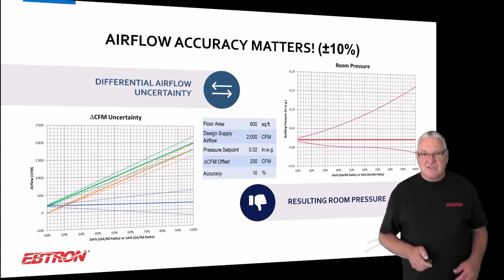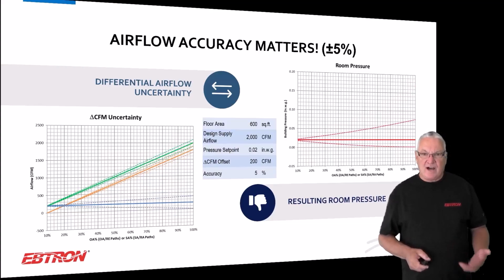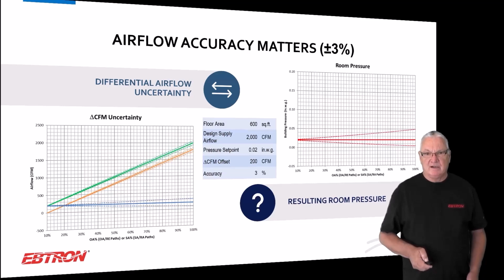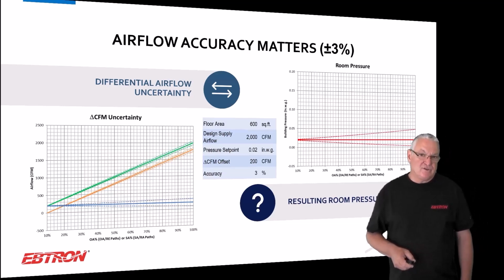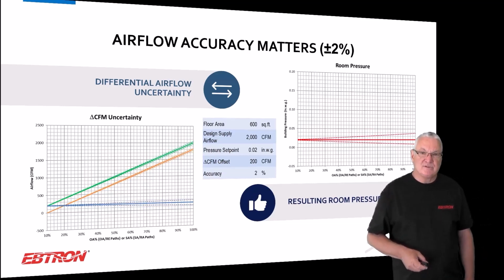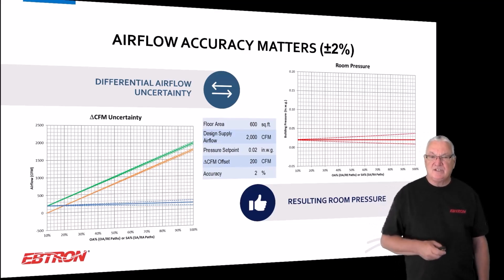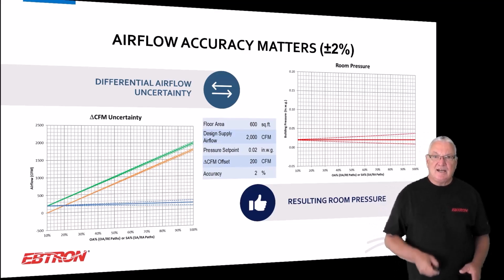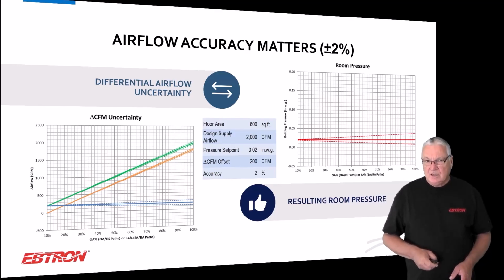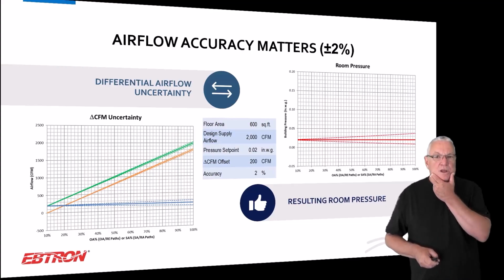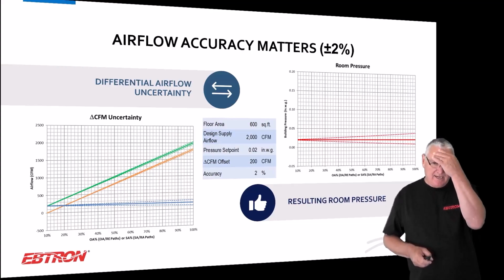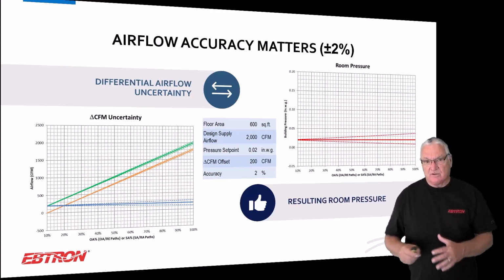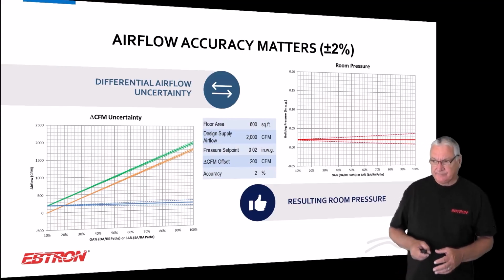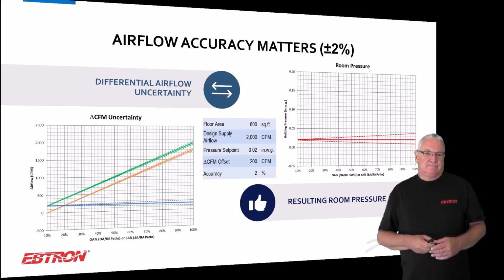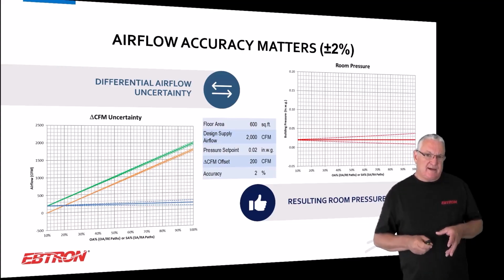Okay, so 10% on this example doesn't work, 5% isn't really much better. 3% is still marginal, and in this case, you'd have to get to 2%. And this is a pretty leaky space. If this space was even tighter, the tighter the space, the harder it is to control it. So as spaces get tighter and tighter, the control gets harder and harder. So that's something I want you to think about.